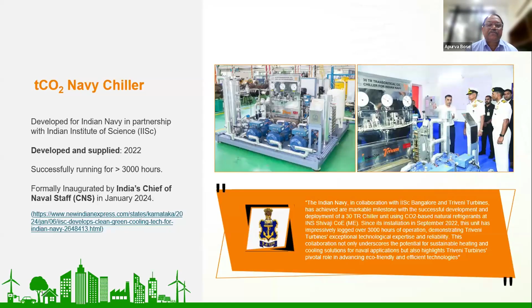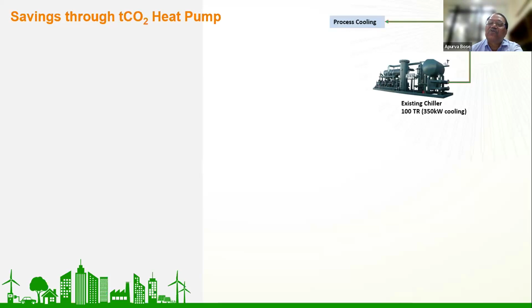Moving on, I want to give an example here of savings through transcritical CO2 heat pump. Let's assume you have an existing chiller of 100 TR capacity, which is giving a process cooling temperature of 7 degrees Celsius, and the return temperature is 12 degrees Celsius. So this is how it is working.